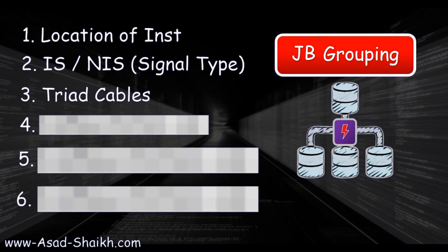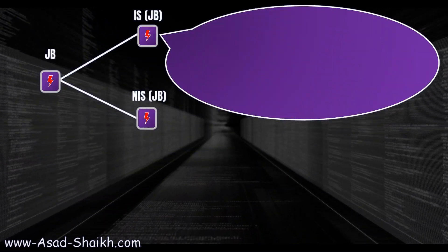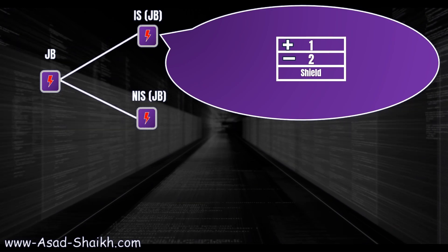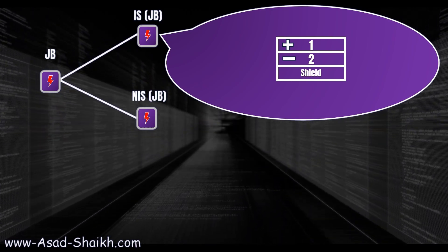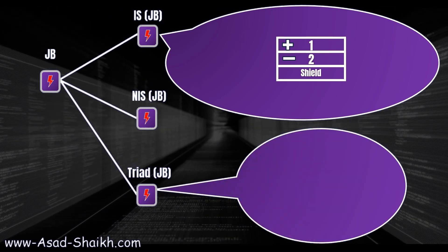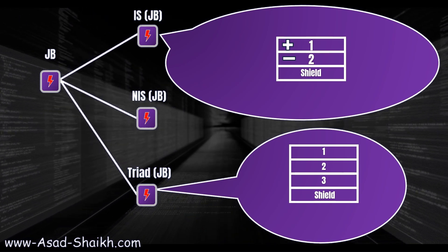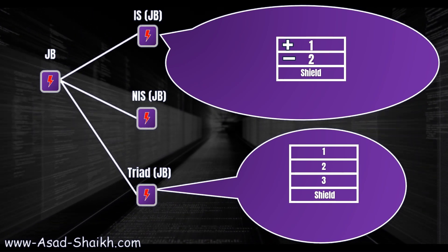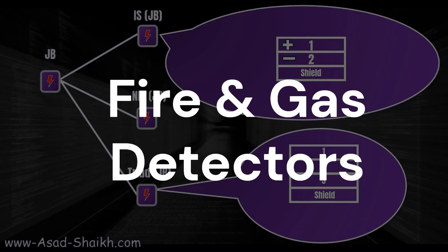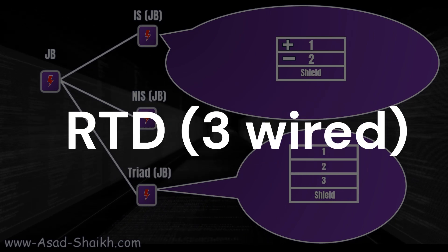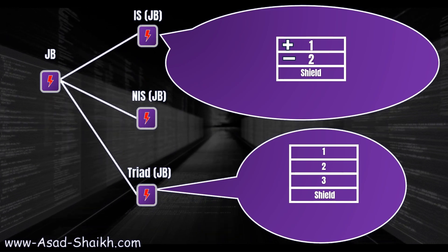The third important criteria is triad cables. For a standard IS JB you have two terminals — positive, negative, and shield. But for a triad cable the connection is different: you have three wires plus a shield. For this reason it is sometimes preferred to have a separate triad cable JB. Common examples of triad cable devices include fire and gas detectors and RTDs.